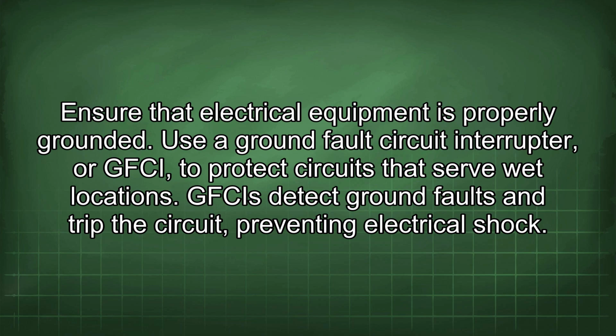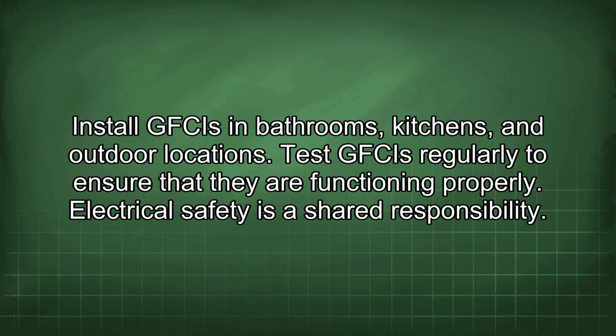Use a ground fault circuit interrupter, or GFCI, to protect circuits that serve wet locations. GFCIs detect ground faults and trip the circuit, preventing electrical shock. Install GFCIs in bathrooms, kitchens, and outdoor locations. Test GFCIs regularly to ensure that they are functioning properly.